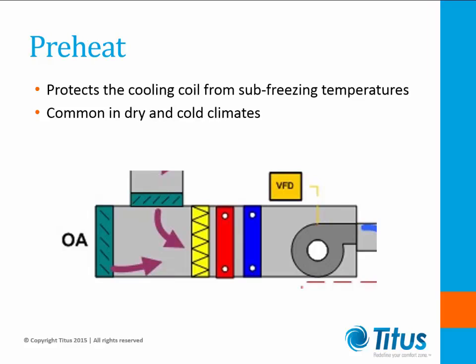Let's start with the preheat configuration. Many of you have looked at the last slide and asked, well, why is the heating coil in front of the cooling coil? We see this question from time to time, and there's no right or wrong to this. This configuration is known as a preheat configuration. The heating coil protects the cooling coil from sub-freezing temperatures. This configuration is typically found in dry and cold climates.